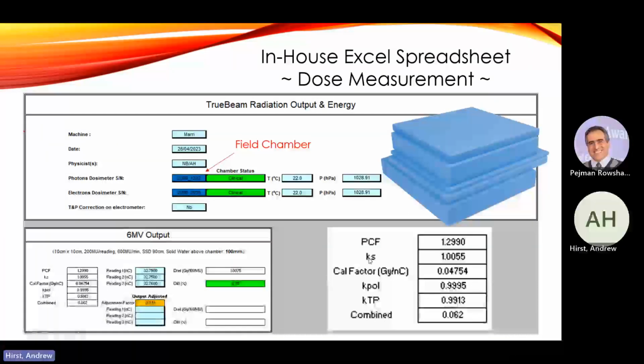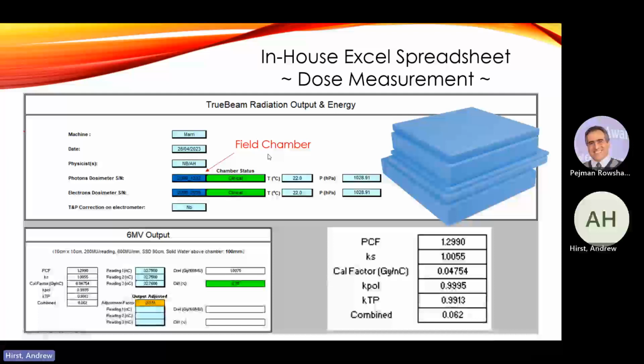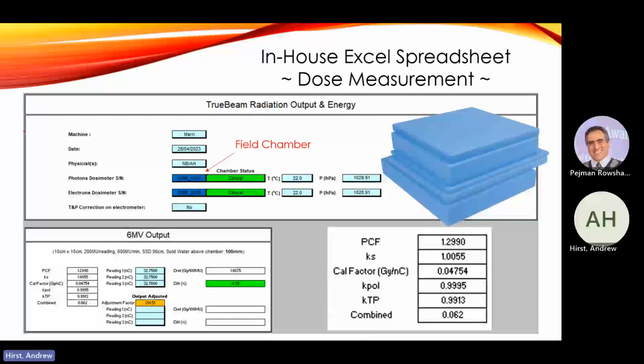So KS was our recombination factor that we calculated with the chamber. Our Cal factor, this is a cross-calibration factor from the reference chamber. So again, I just want to stress this is a field chamber at this point. Kind of has like a tertiary standard. Polarity, temperature and pressure correction, and then everything combined. Now this PCF one I wanted to mention, this is because in monthly measurements we don't use water. If you're doing reference dosimetry, strictly you should use water for determining the true dose at that point. If you're doing it just for your QA, you can use solid water. TRS 398 says that's okay. You just need to have some kind of factor that converts between the two. So that's PCF.